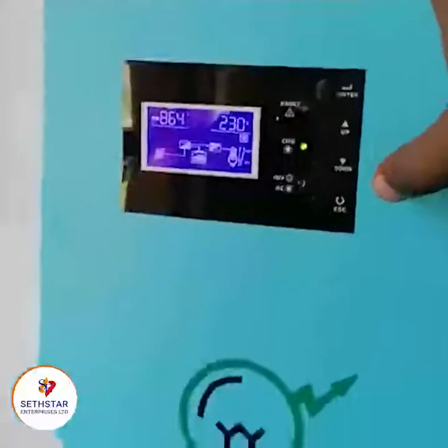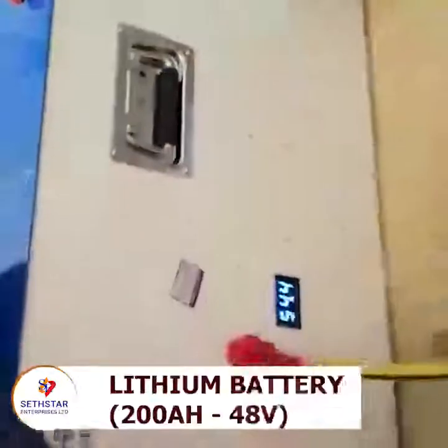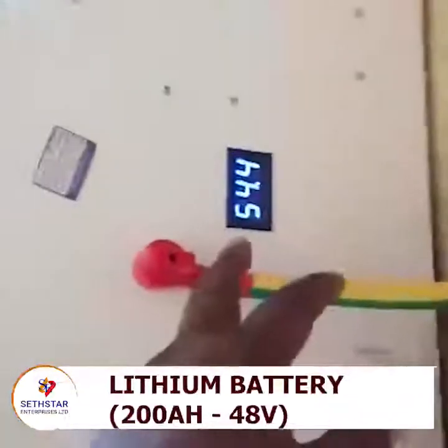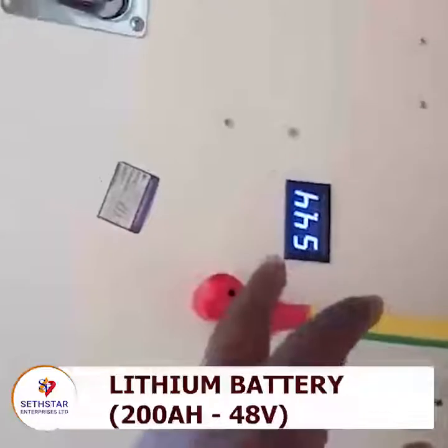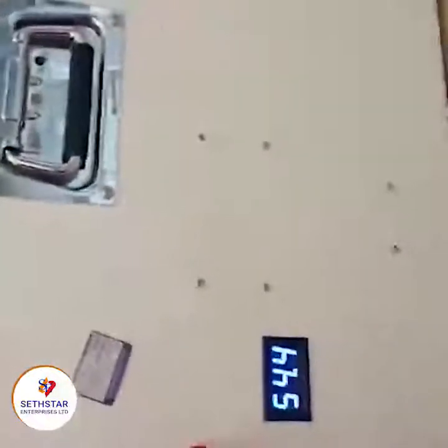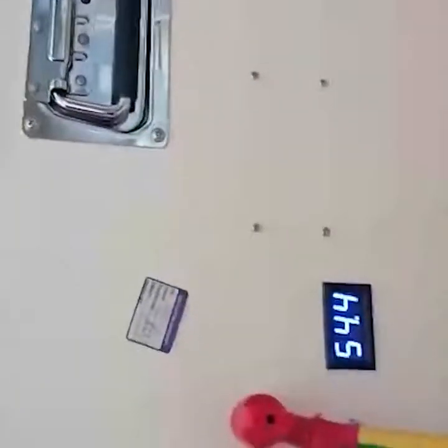The battery is storing at the same time — this is the best system one can have, either off-grid or on-grid. We are using a lithium battery of 200 amp-hours, 48 volts. At this moment it is at 54.4 volts, and there is still power going through the loads, keeping the battery in a very stable state.